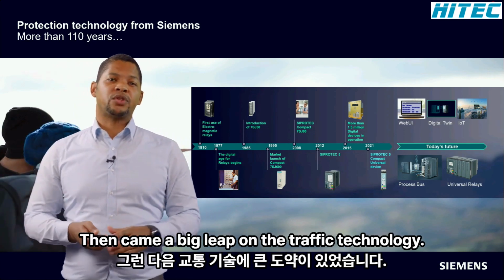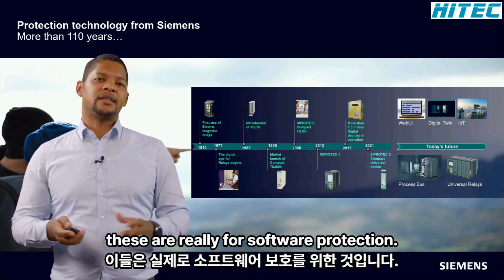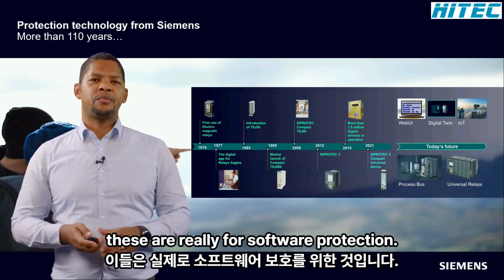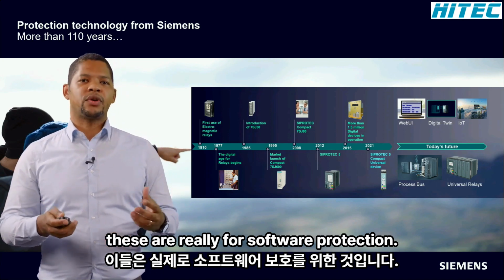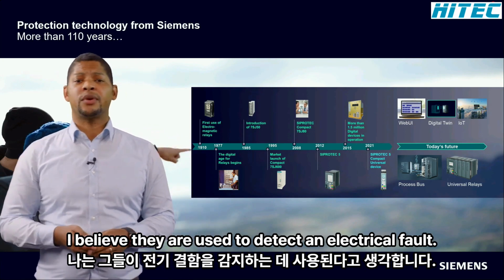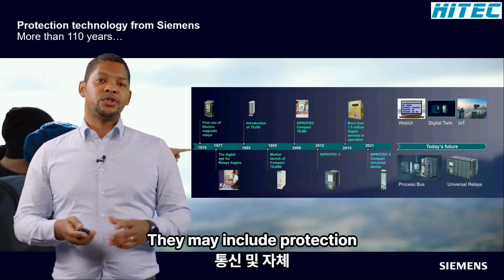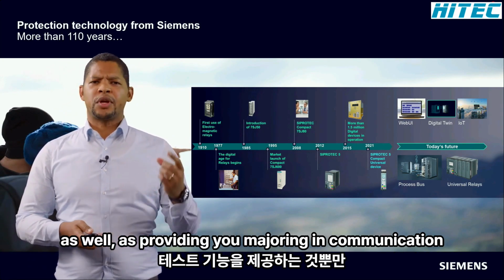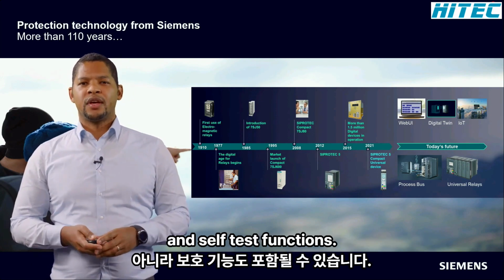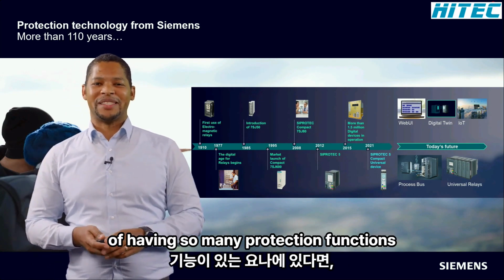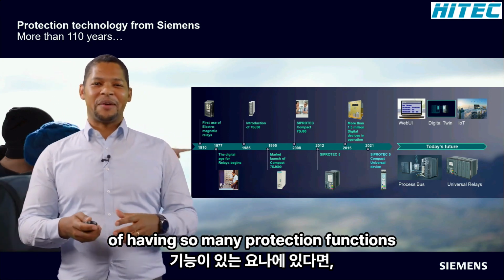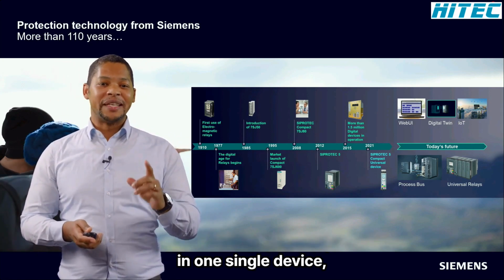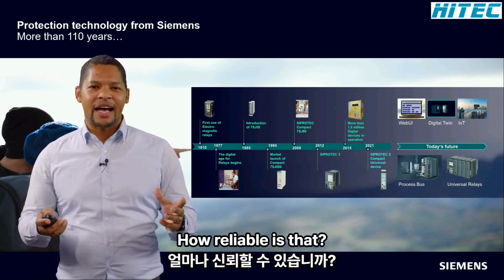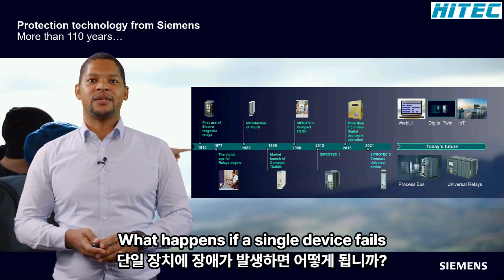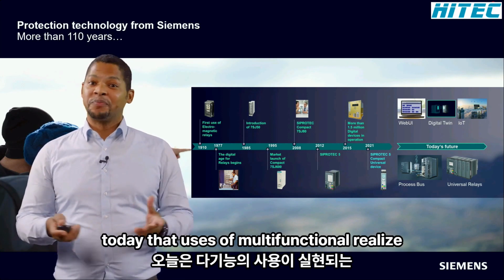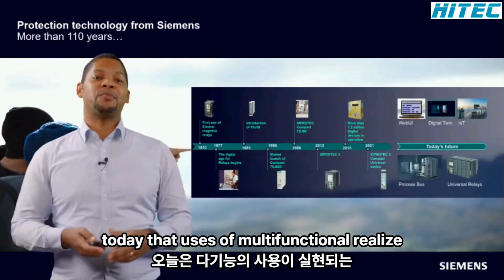Then came a big leap and disruptive technology, the microprocessor-based digital relay. Digital relays are computer-based systems where software-based protection algorithms are used to detect electrical faults. They may include several protection functions in one unit, as well as providing metering, communication, and self-test functions. If you are as young as I am, you may recall the discussion about having so many protection functions in one single device. How reliable is that? What happens if a single device fails? Oh, we're not protected. Well, today, the usage of multifunctional relays is a standard.